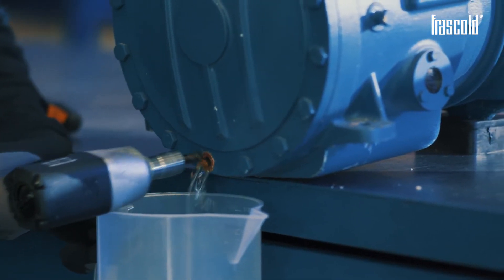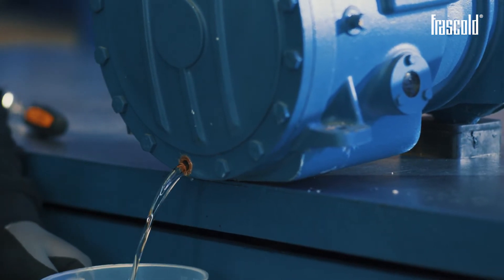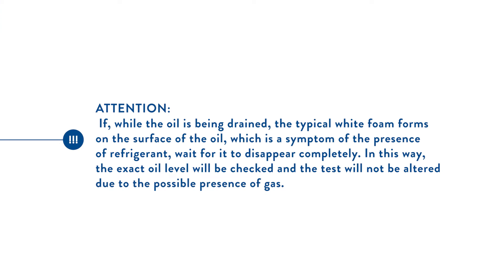Remove the oil drain screw with a screwdriver or ratchet and drain the oil into one or more clean jugs. Attention! If, while the oil is being drained, the typical white foam forms on the surface of the oil — which is a symptom of the presence of refrigerant — wait for it to disappear completely. In this way, the exact oil level will be checked and the test will not be altered due to the possible presence of gas.